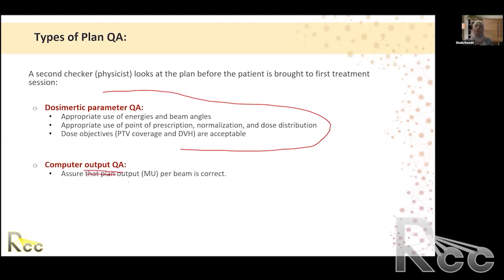And this is where we're going to focus on. This is the monitor unit verification. The plan could be perfect in terms of geometry, setup, and what you see on the screen. However, in order to deliver that plan, the linear accelerator only knows one thing, monitor unit. That's your beam on time. And if that was not correct for whatever reason, the plan will not be delivered properly. So that's what we're looking at.